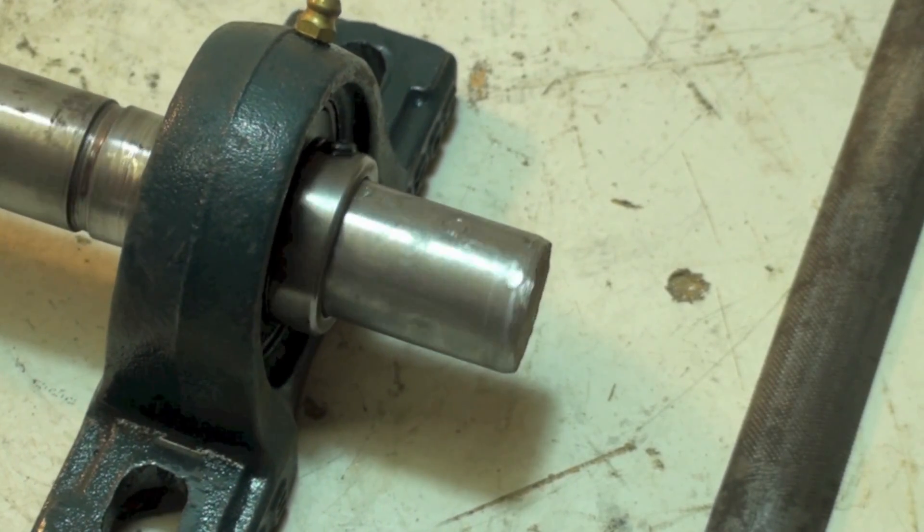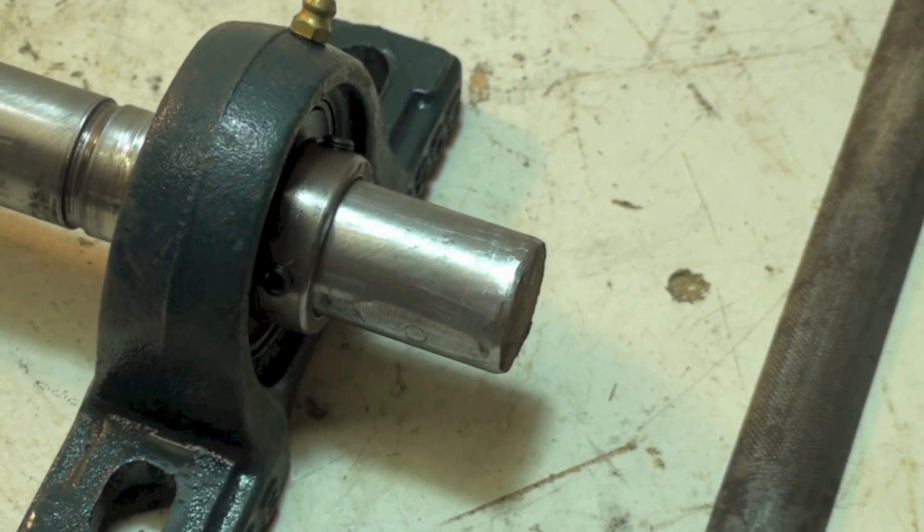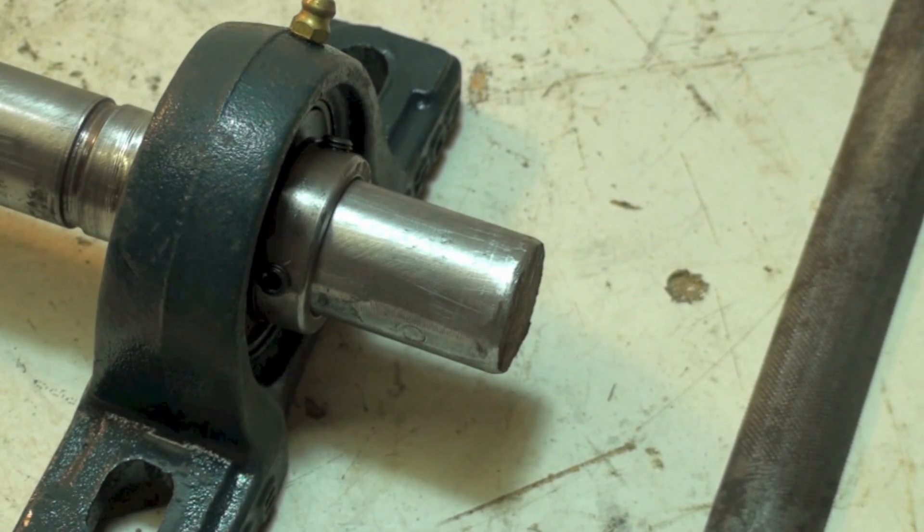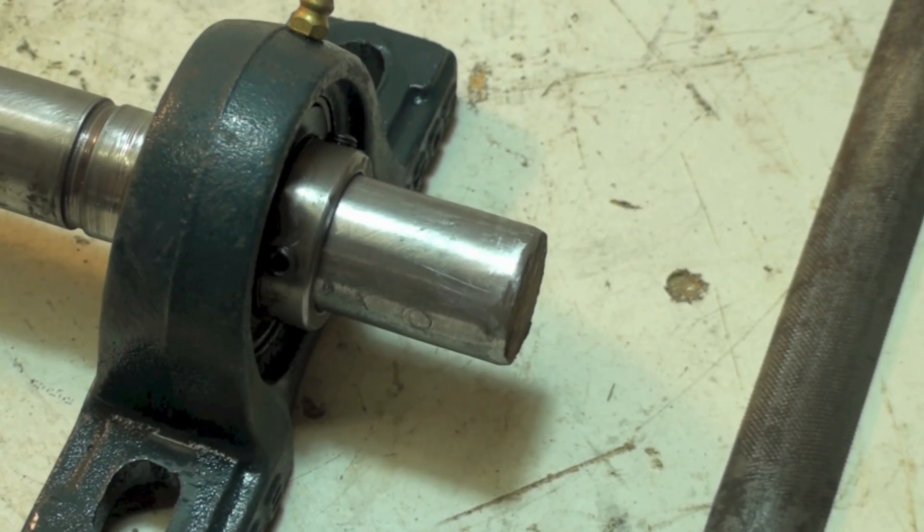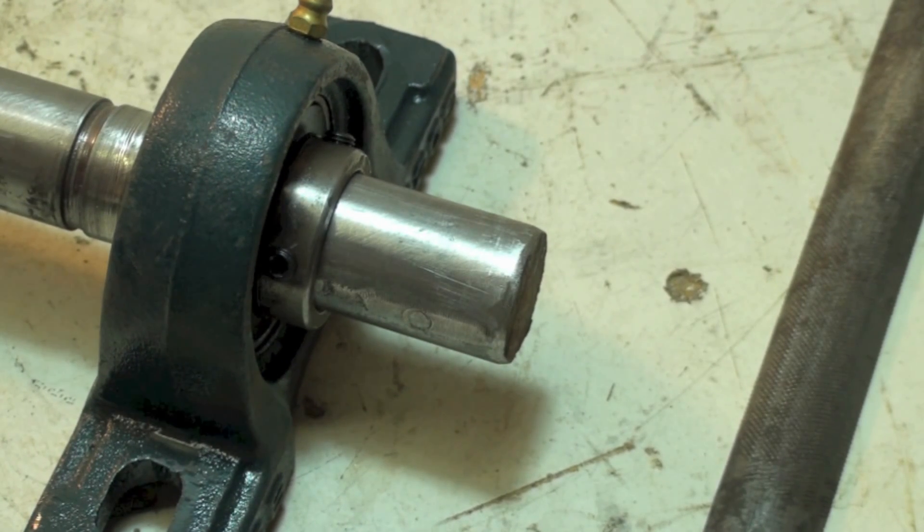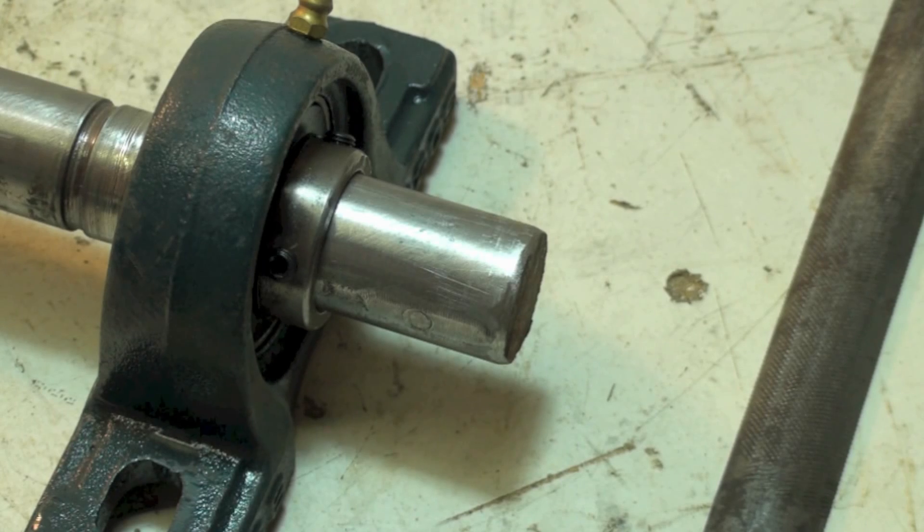But this will ride true, and you've got a repair where you have not had to take the entire blower apart, which sometimes can trash the blower wheel and whatever. So, a fairly quick and easy fix for the failed bearing that has damaged the shaft.